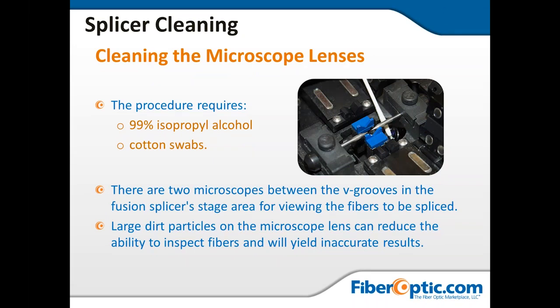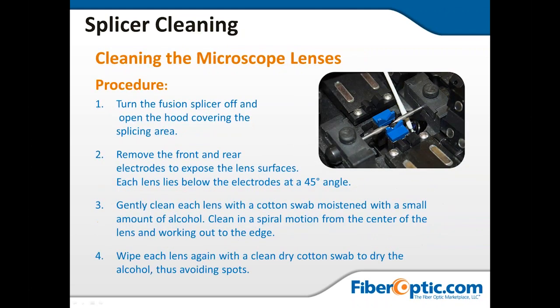There are 2 microscopes between the V-grooves in the fusion splicer stage area for viewing the fiber to be spliced. Large dirt particles on the microscope lenses can reduce the ability to inspect fiber and will yield inaccurate results. Cleaning the microscope lenses procedure.